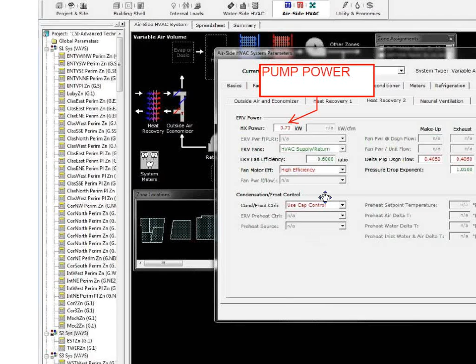So the pump power on the runaround loop, I figured I could put in as heat exchanger power, and that's all I did. That power is the power of the pump motor, so when it's on, it's going to be using that power, which is what happens with the runaround loop. The pump runs and just circulates. For the pressure drops, I used the same water pressure drops.